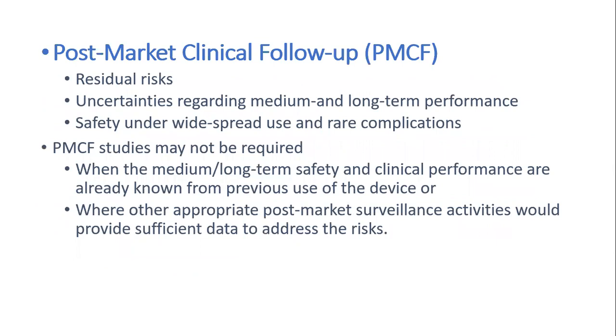Coming to post-market clinical follow-up, PMCF activities are taken up for the products which are already CE marked and available in the market.